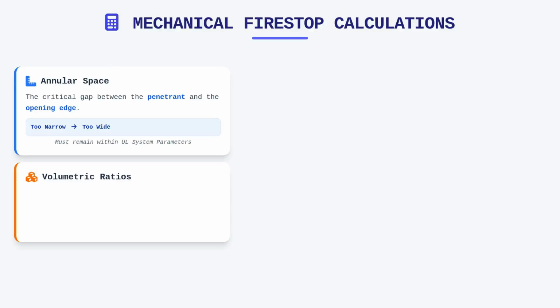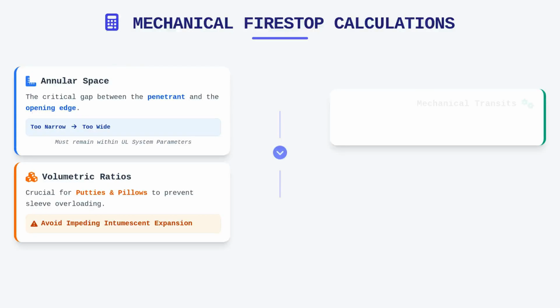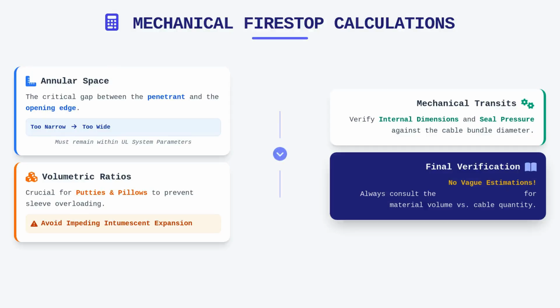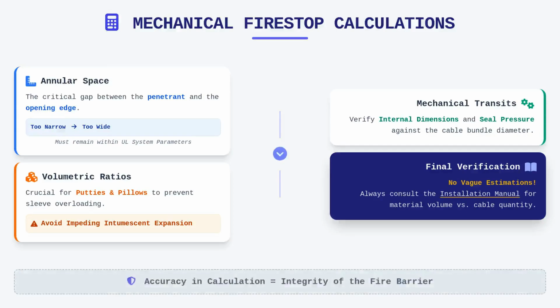Volumetric fill ratios are particularly important when using Firestop putties or pillows to ensure that we do not overload a sleeve, which could impede the expansion of intumescent materials. If a mechanical transit system is used, we must verify the internal dimensions and the seal pressure against the cable bundle diameter. Relying on vague estimations is insufficient. One must verify the specific installation manual for every product to ensure the volume of material provided is sufficient for the diameter and quantity of cables penetrating the barrier.